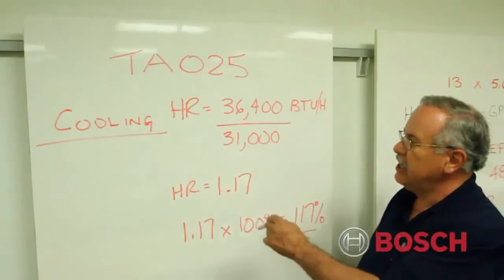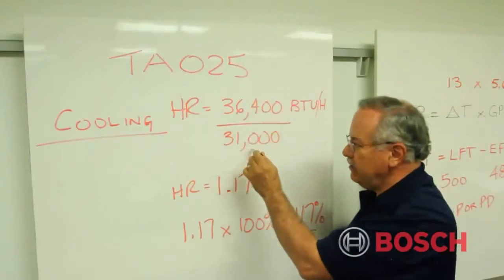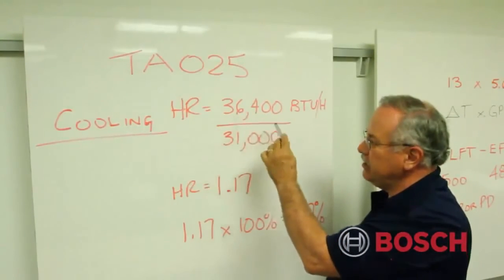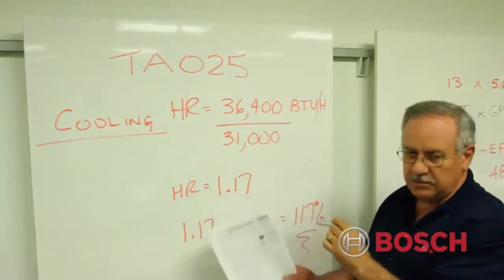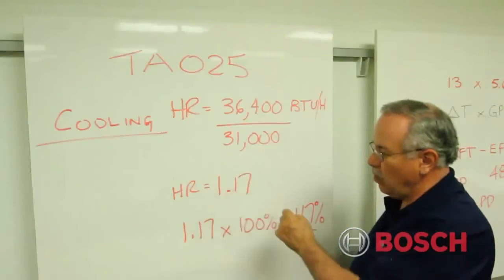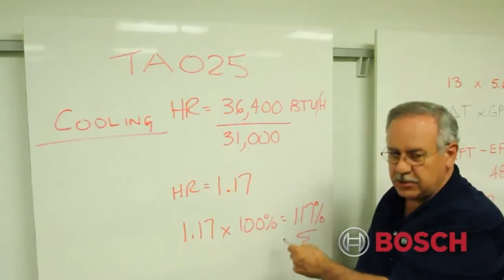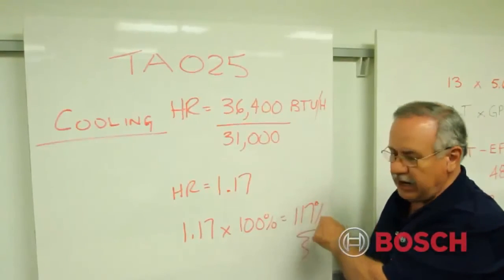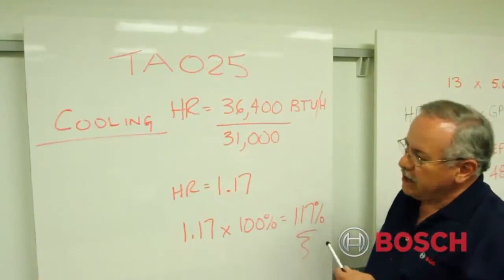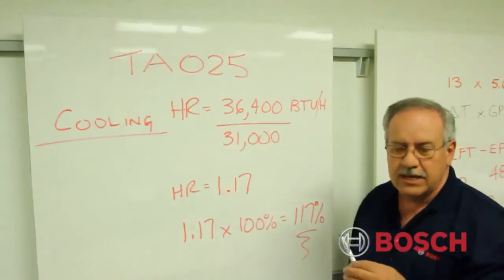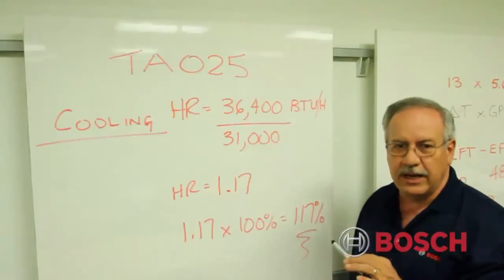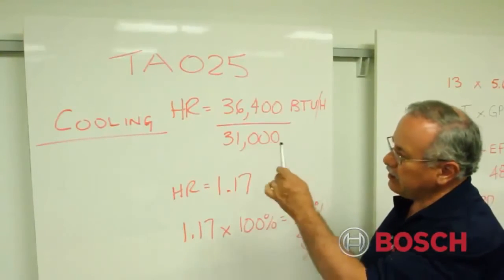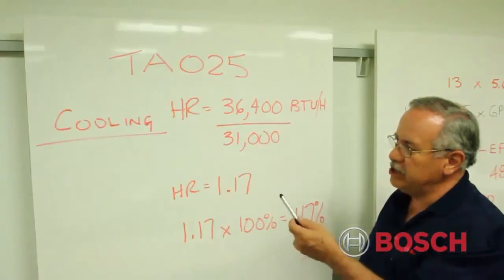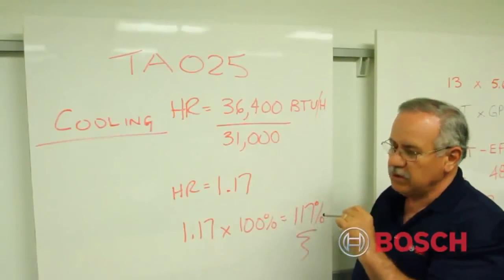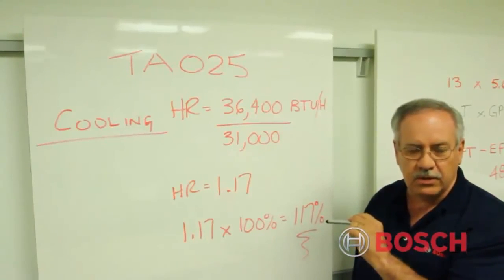So the way to determine how well this machine is running at these particular conditions is what we found, actual divided by specified. So actual at 36,400 divided by approximately 31,000 from the specs, and we come up with an answer of 1.17. We convert that to percentage by multiplying by 100%, and we are operating at approximately 117%. The Bosch criteria for cooling or heating is a minimum of operation of approximately 90% or better. So in this particular case, if a technician was in the field and checked it the way we have determined and shown you, this would be acceptable to Bosch and should be acceptable to you as well as the consumer.